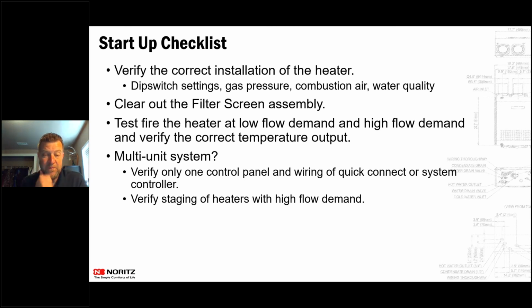If you are installing more than one unit, we can multi-system control up to 24 units at the same time. If you are using two units with a quick connect cord going between the two, make sure you turn on enough water that it's actually going to kick on the second unit, so that both units are firing and staging between each other. If you're putting two units together, it's a larger home. Those units are going to modulate which one's primary and which one's secondary. Every 8 hours of burn, it'll switch over which one's primary and which one's secondary, so you get very even usage over the units over time, versus doing two tanks in parallel where the first one does all the work and the second one is kind of just a storage tank. To do that, it's just a simple little cord that connects the two together if you're doing two units. If you're doing three units or more, then it is a system controller that you would put in there to control the whole system.